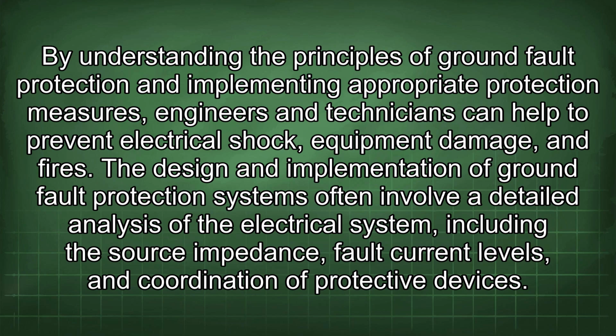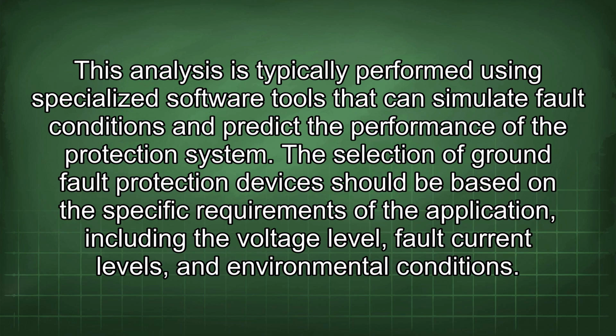By understanding the principles of ground fault protection and implementing appropriate protection measures, engineers and technicians can help to prevent electrical shock, equipment damage, and fires. The design and implementation of ground fault protection systems often involve a detailed analysis of the electrical system, including the source impedance, fault current levels, and coordination of protective devices. This analysis is typically performed using specialized software tools that can simulate fault conditions and predict the performance of the protection system. The selection of ground fault protection devices should be based on the specific requirements of the application, including the voltage level, fault current levels, and environmental conditions.